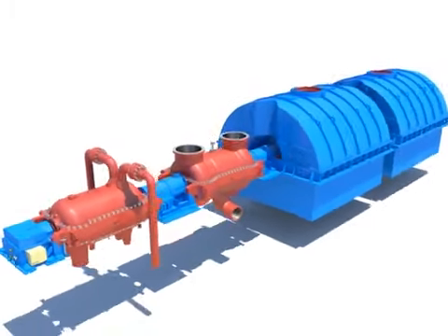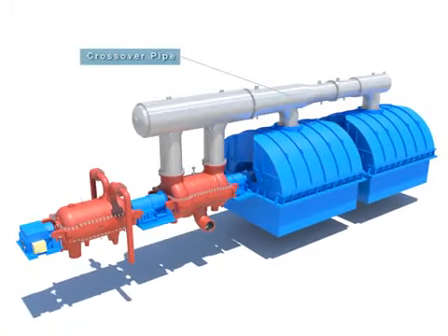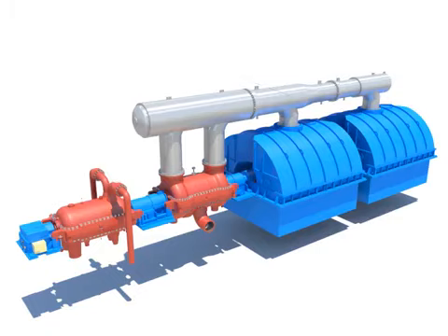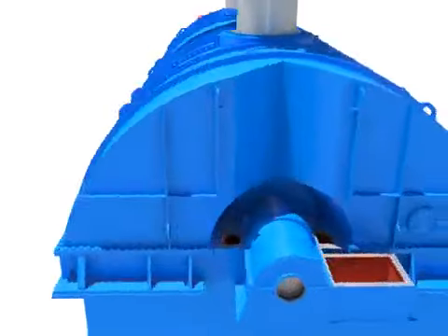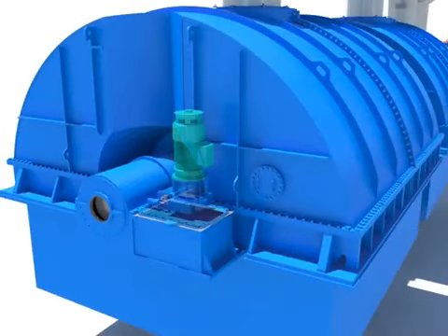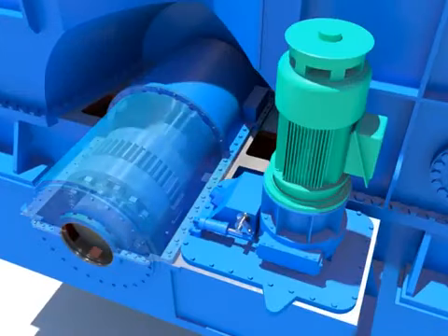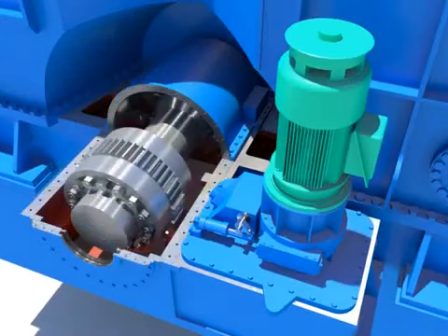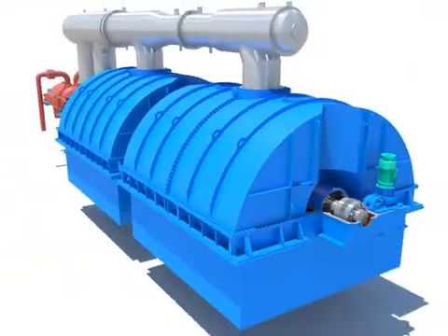The crossover pipe is a steam path to send the intermediate pressure turbine exhaust to the low-pressure turbine. The turning gear smoothly makes the speed increase when the steam flows in by slowly rotating the turbine axial when the turbine stops or during the period for starting preparation. Also, it is installed to constantly cool down the turbine inside parts.